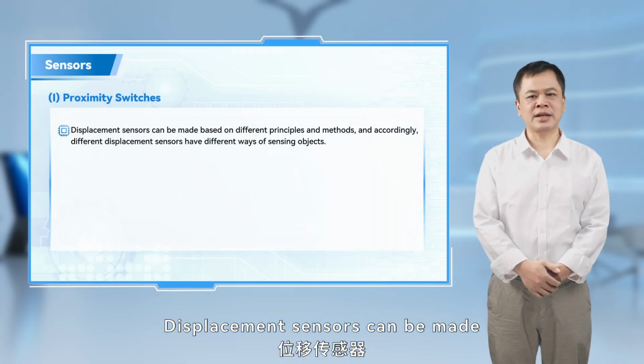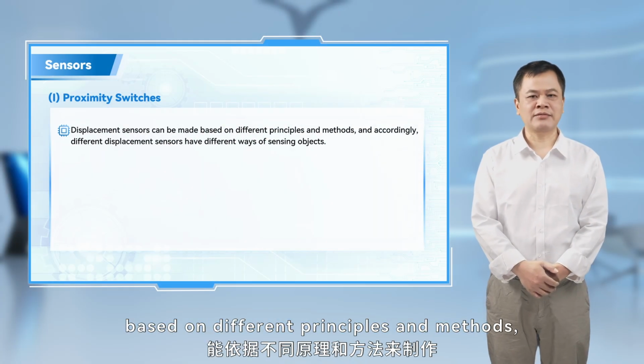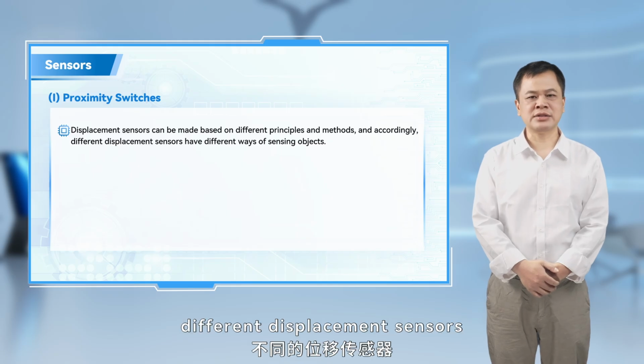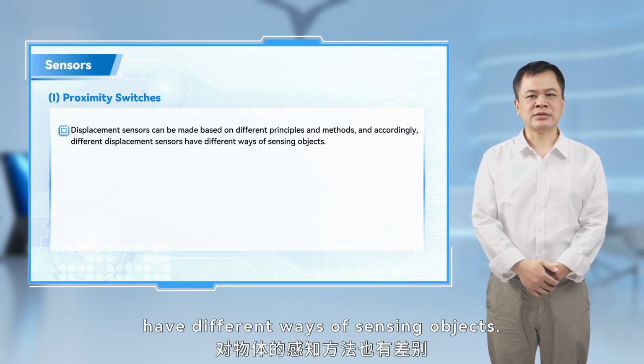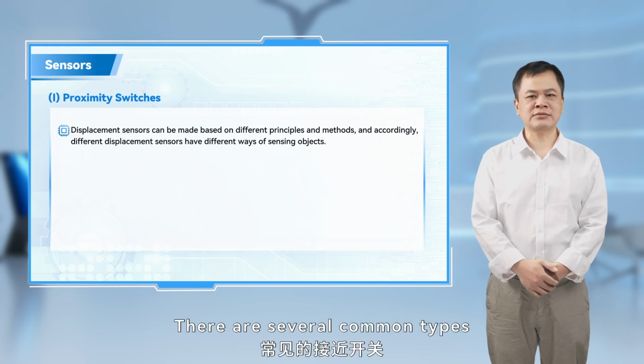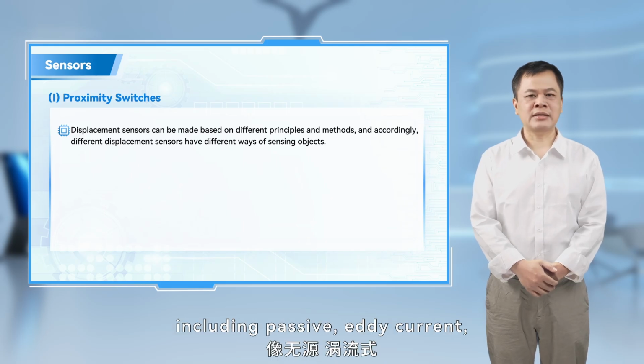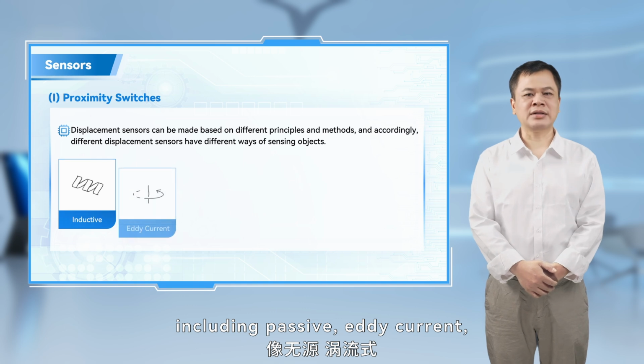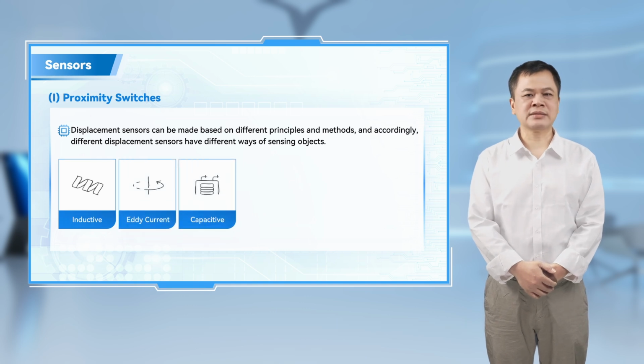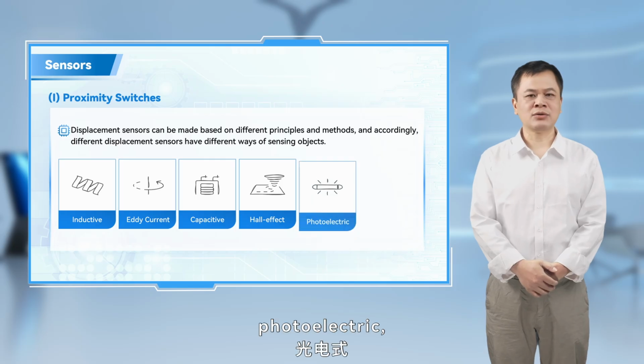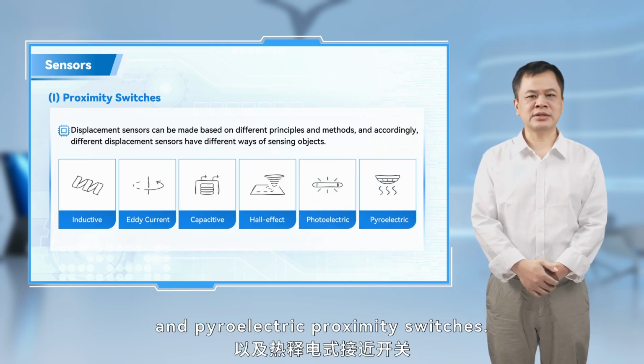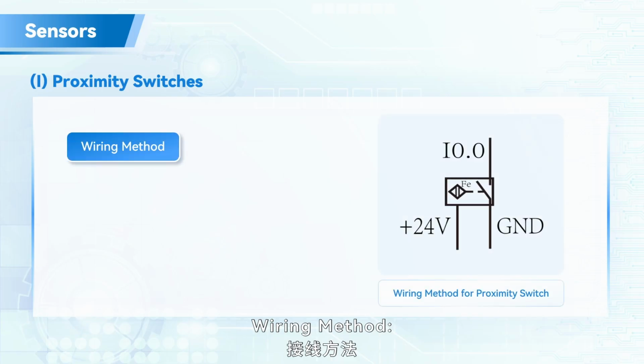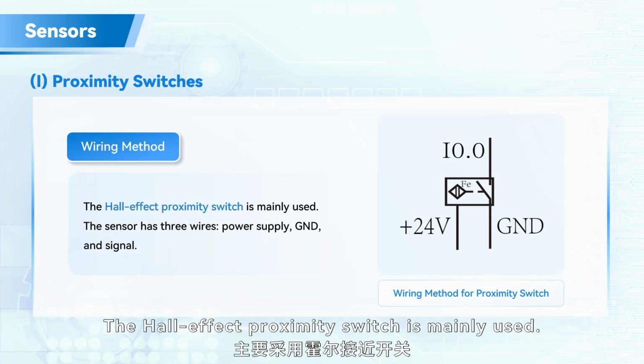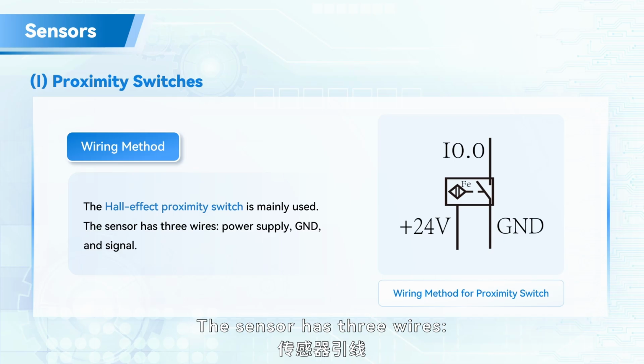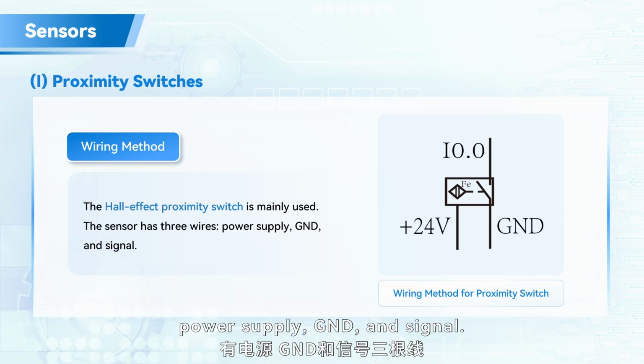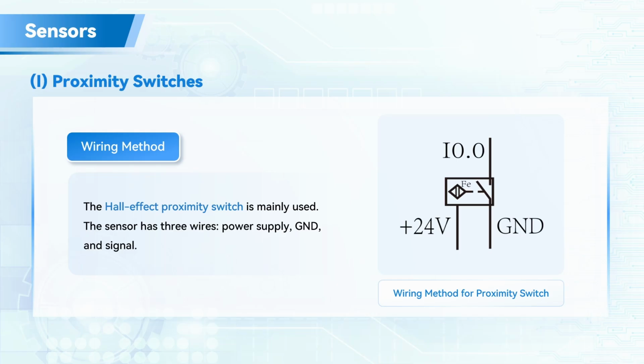Displacement sensors can be made based on different principles and methods, and accordingly, different displacement sensors have different ways of sensing objects. There are several common types of proximity switches, including inductive, eddy current, capacitive, Hall effect, photoelectric and pyroelectric proximity switches. Wiring method. The Hall effect proximity switch is mainly used. The sensor has 3 wires: power supply, GND, and signal.